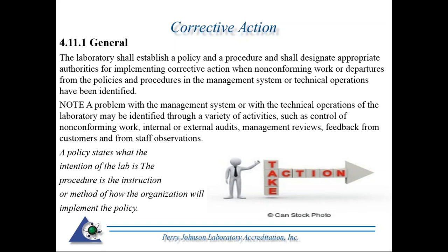17025 requires a policy and procedure. A policy states what the intentions of the lab are. In other words, the lab will institute a corrective action when any of the elements of the quality management system is not being followed or a nonconformance is identified. And then you would have a procedure, which is, okay, you have this policy that's stated. The procedure is the instruction or method of how the organization will implement the policy.